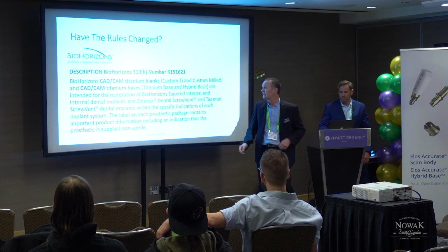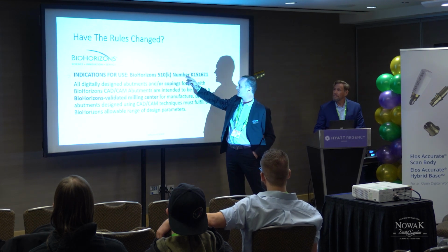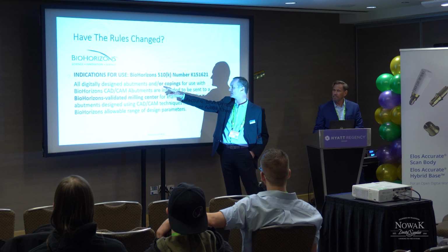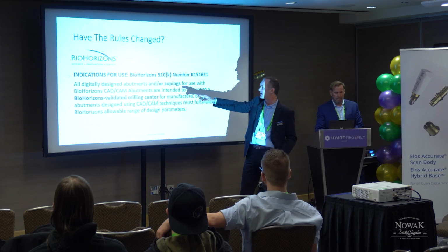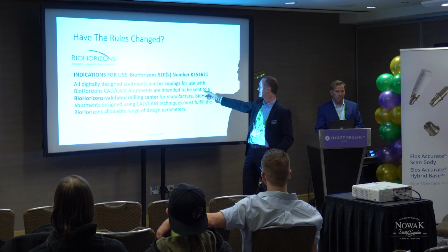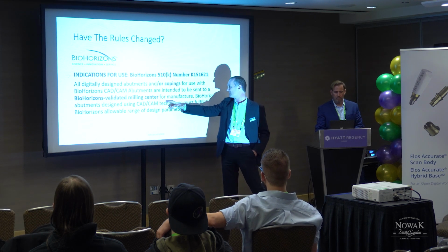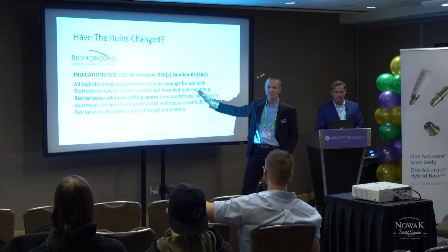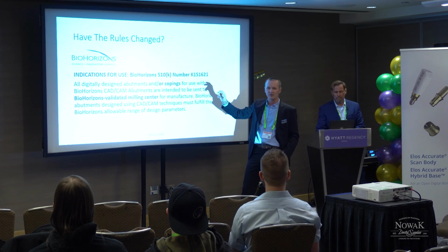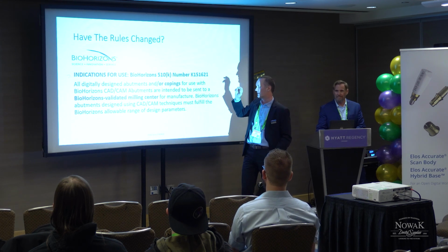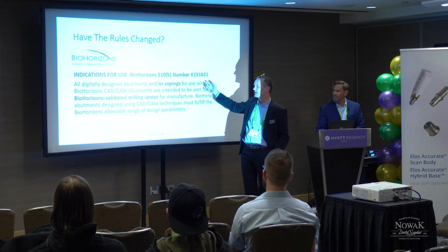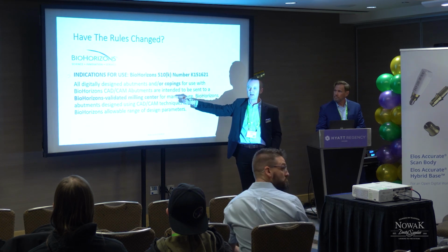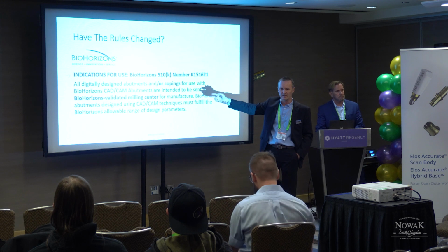If we go to the next one, you will see that specifically FDA tells you you have to write in the indication for use that all digitally designed abutments and all copings for use with BioHorizon CAD/CAM abutments are intended to be sent to a BioHorizon validated milling center for manufacture. This also tells you you cannot do this in your own lab. You cannot mill a crown to put on top of a Ti-Base, or you cannot mill a custom abutment in your own lab using these products with this 510K number unless you have been validated as a milling center by BioHorizons.